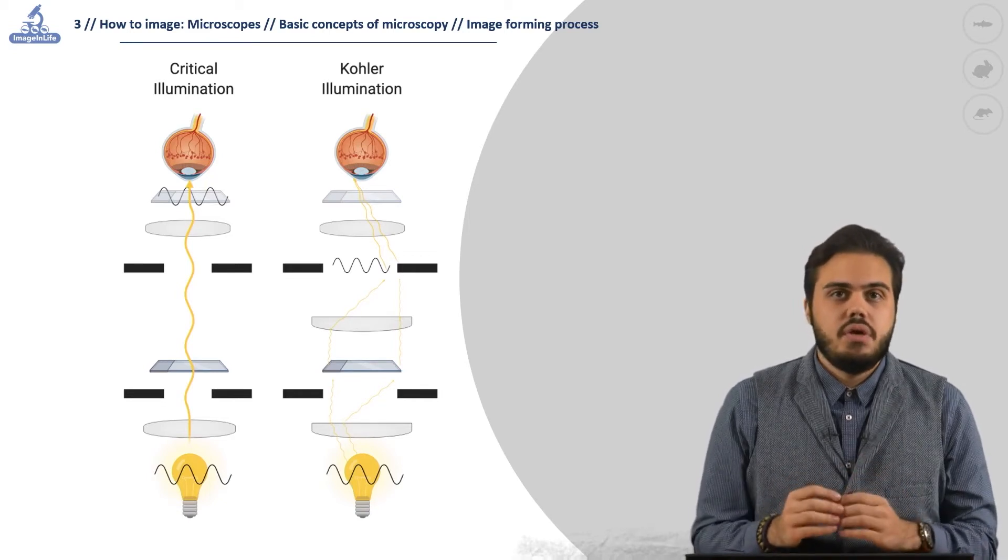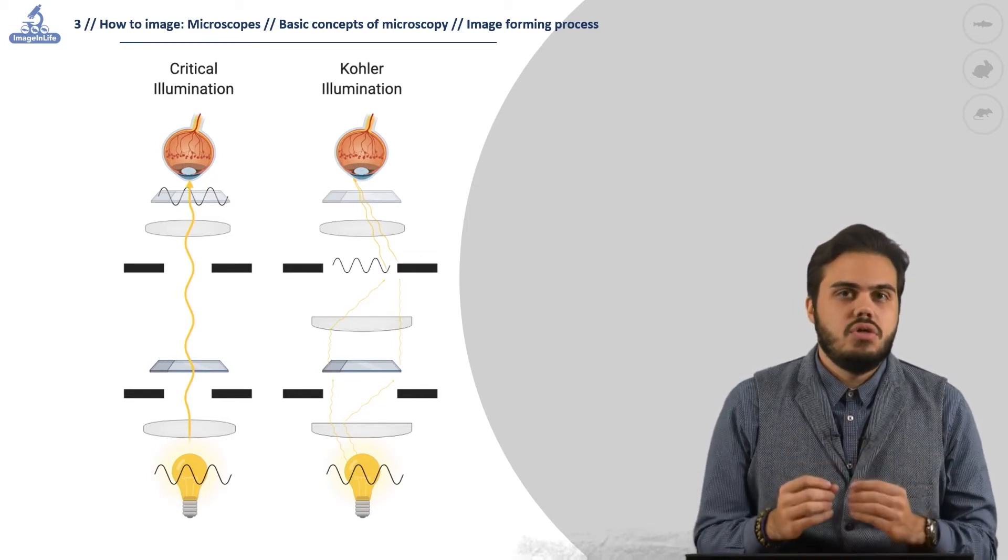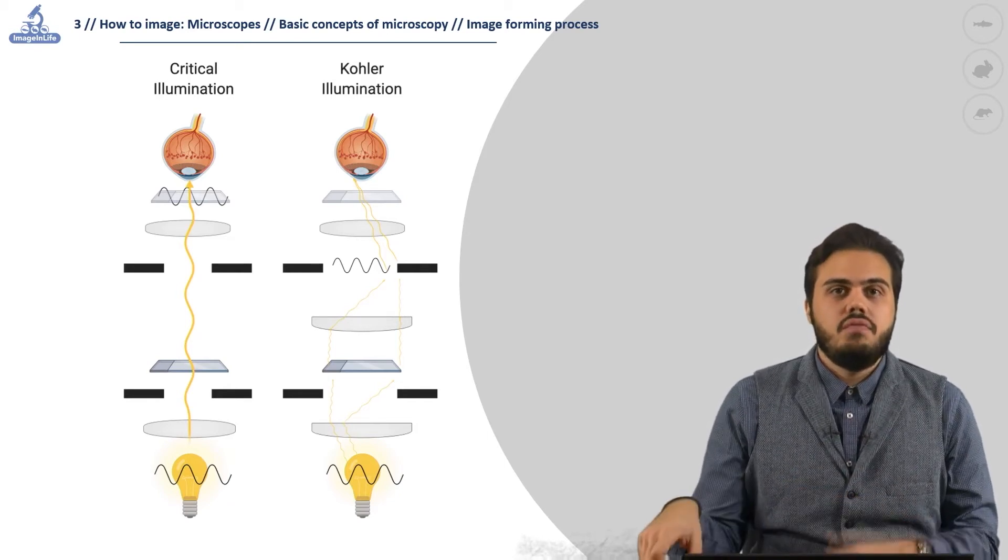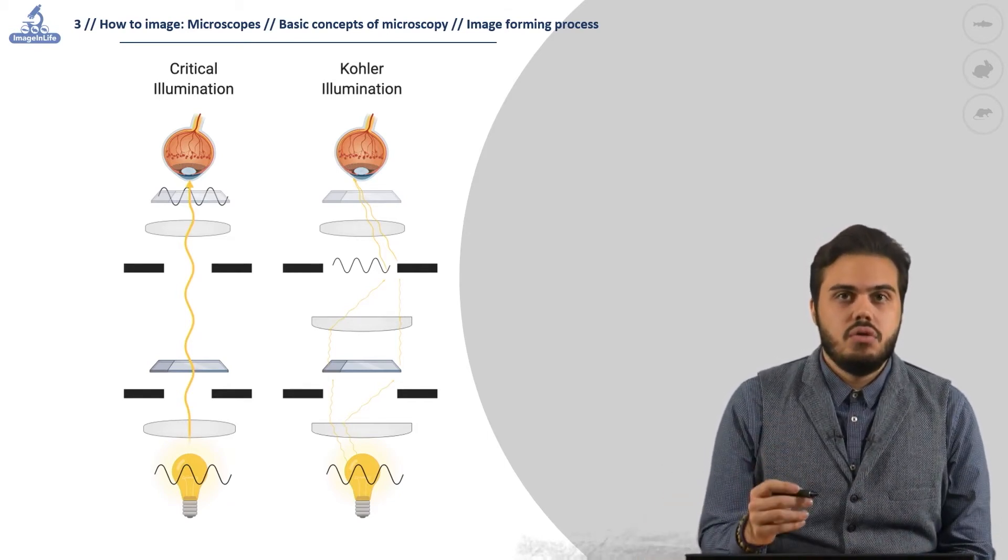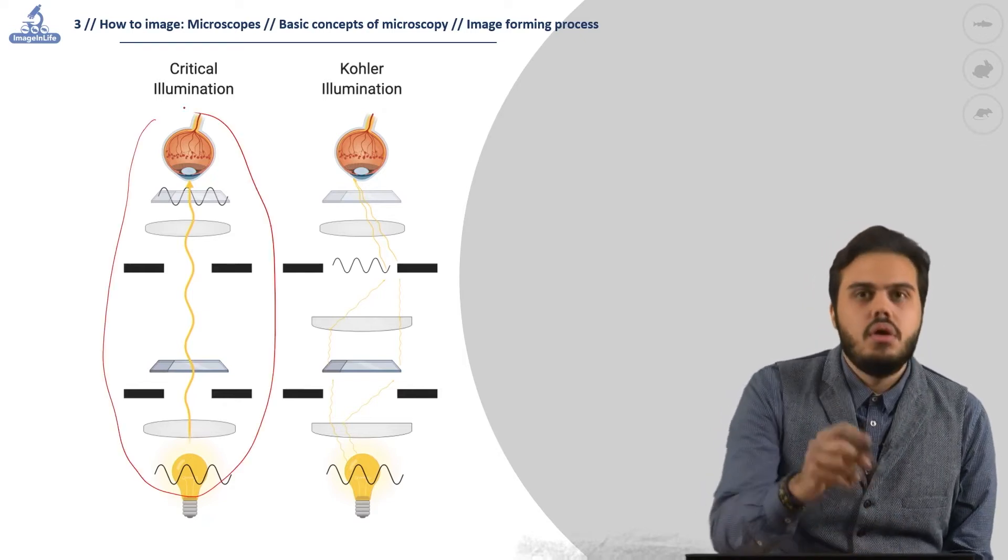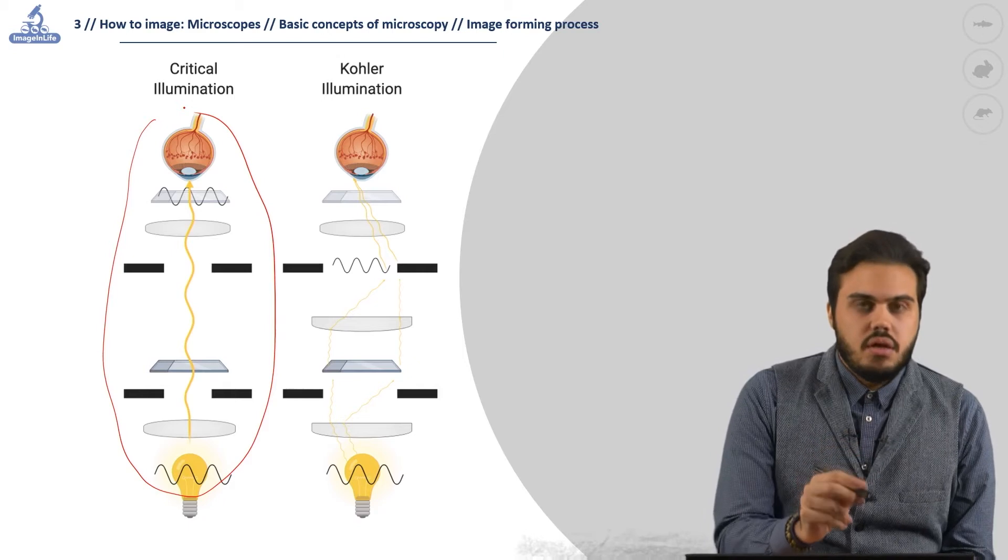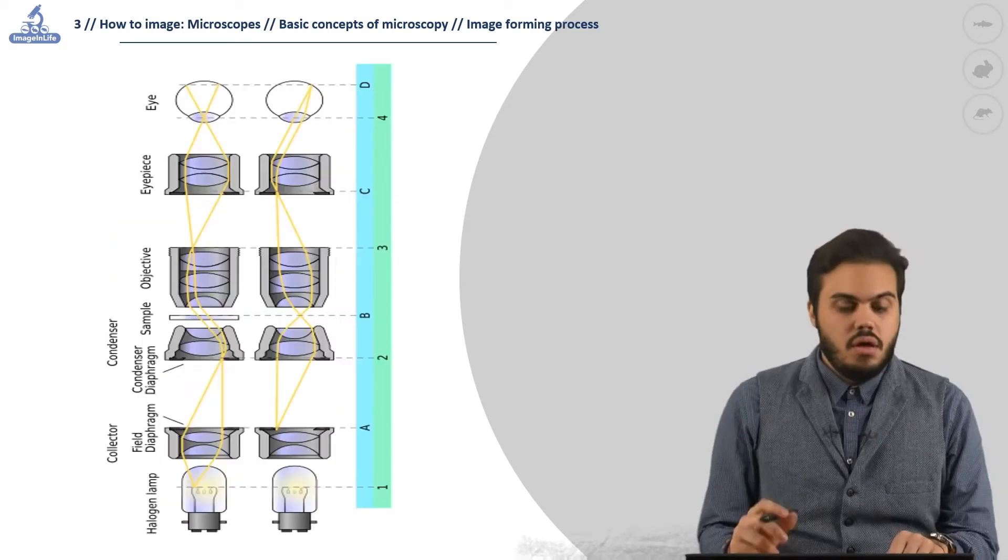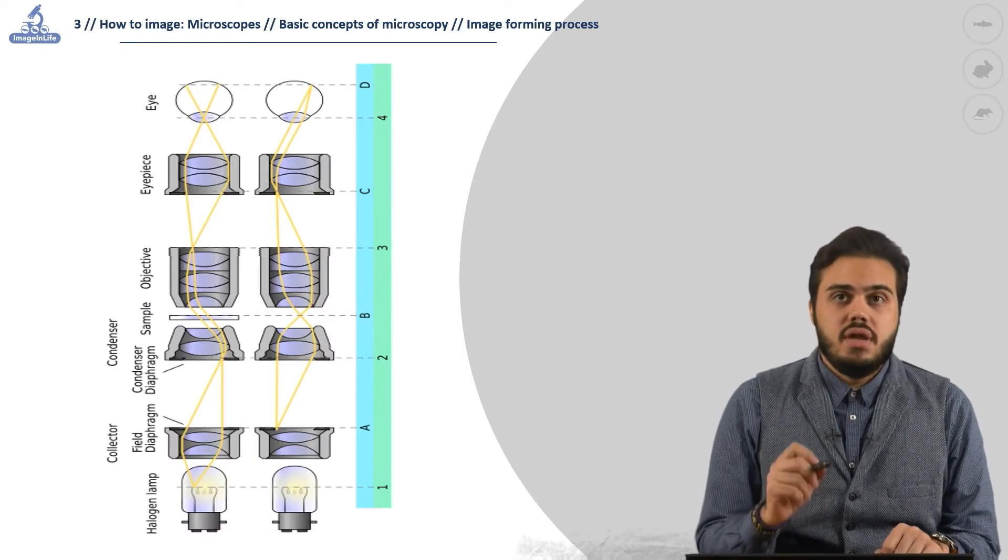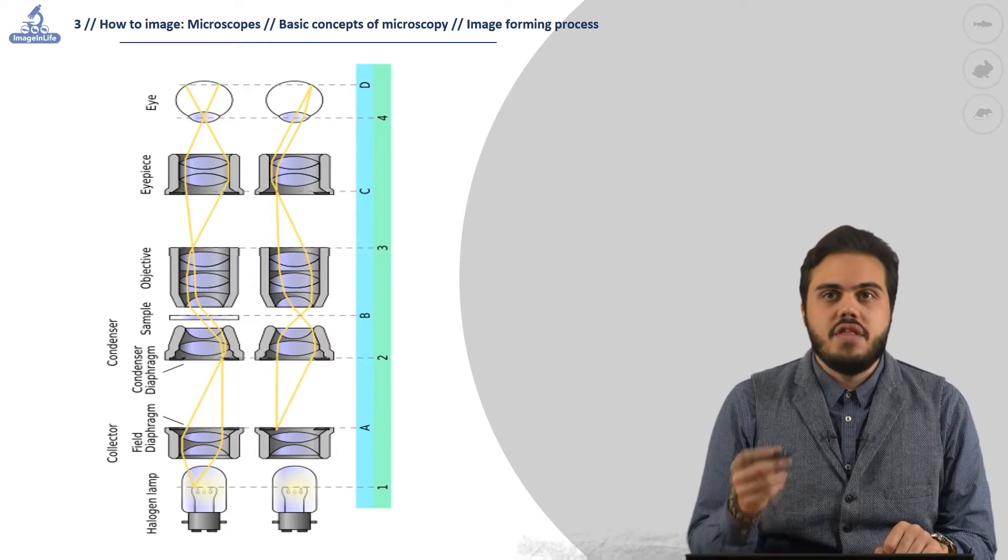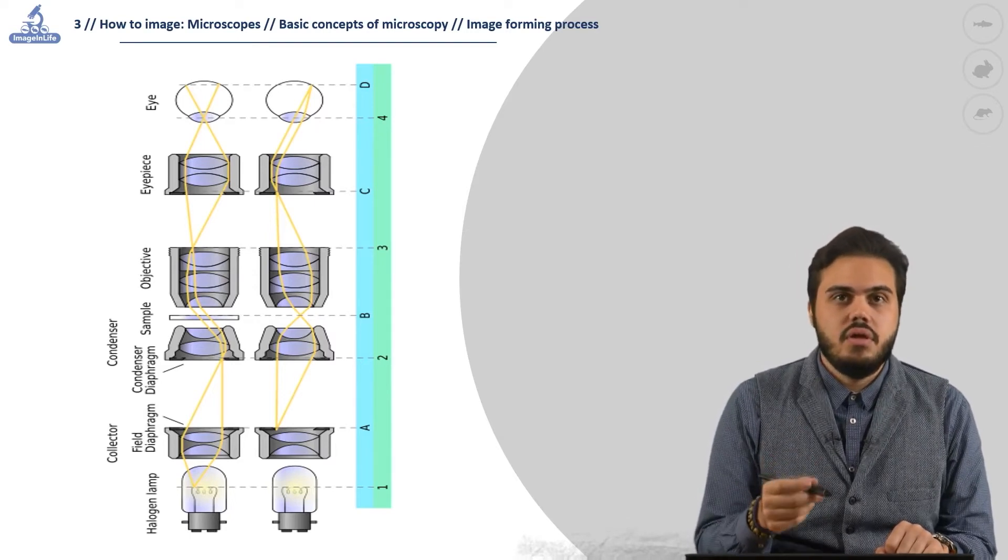A huge step in this direction was the realization of Köhler illumination in 1893. Before the invention of this method of illumination, the most used method was the critical illumination, where the focus plane of the specimen and the lamp are in the same plane. The Köhler illumination places the light source image and the specimen in two different focal planes and the specimen itself is illuminated in a uniform way.